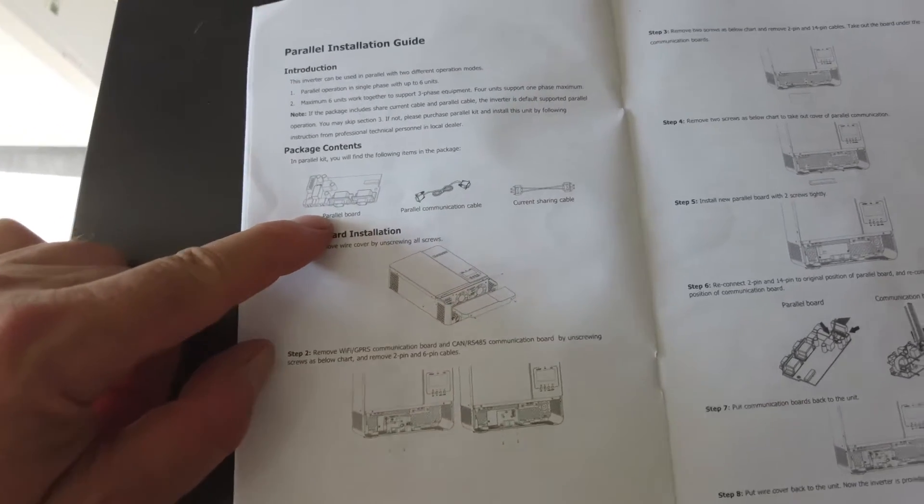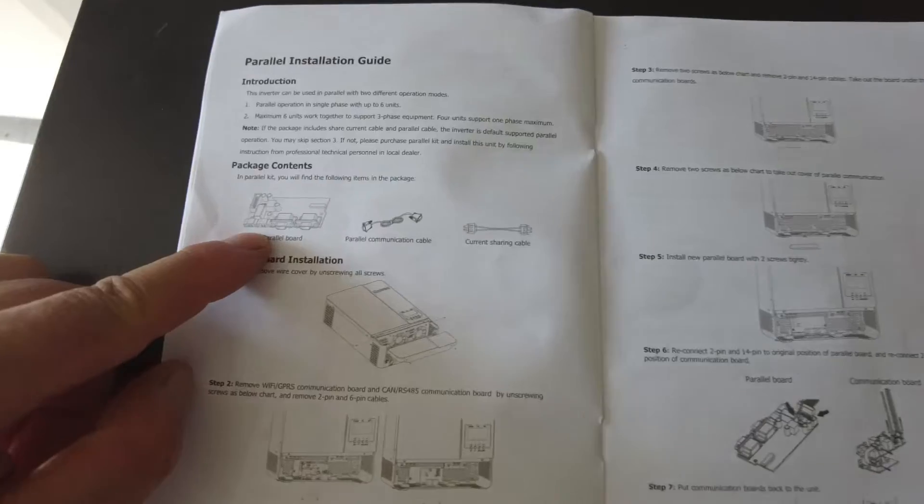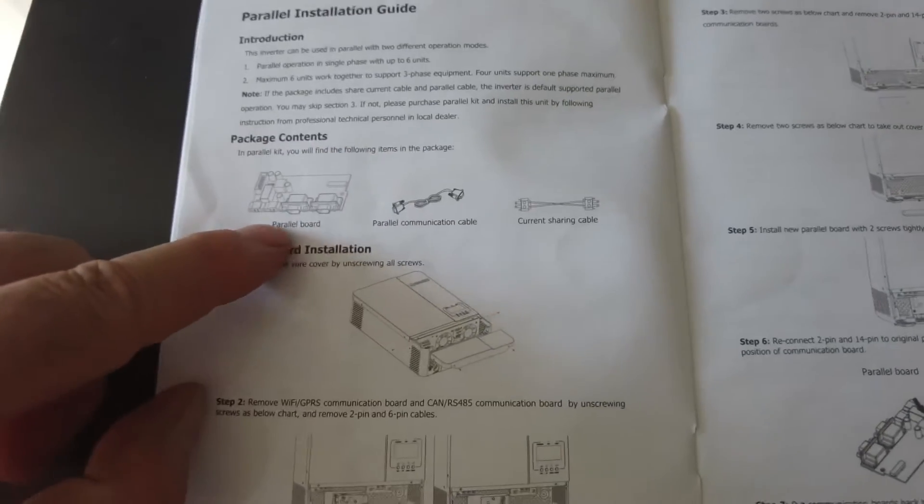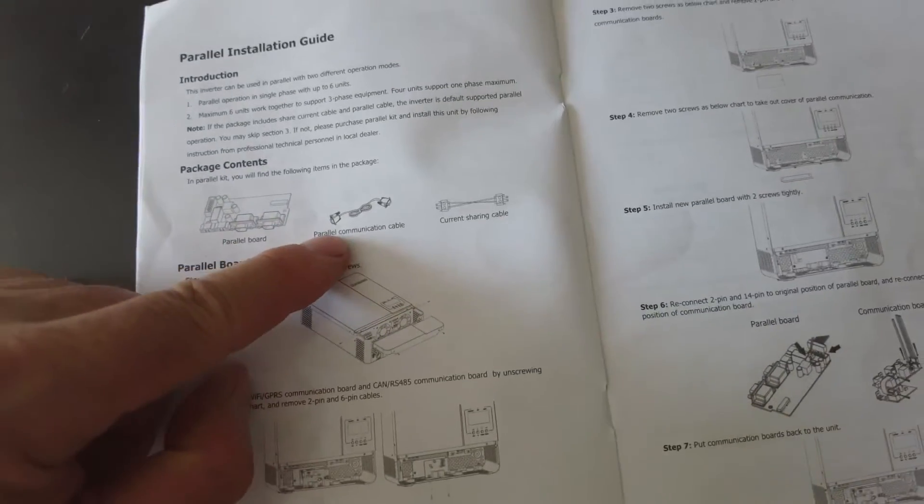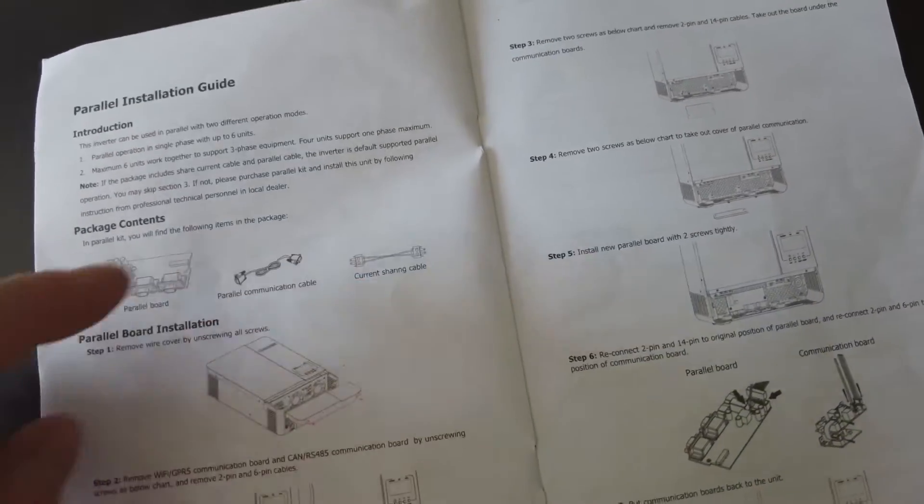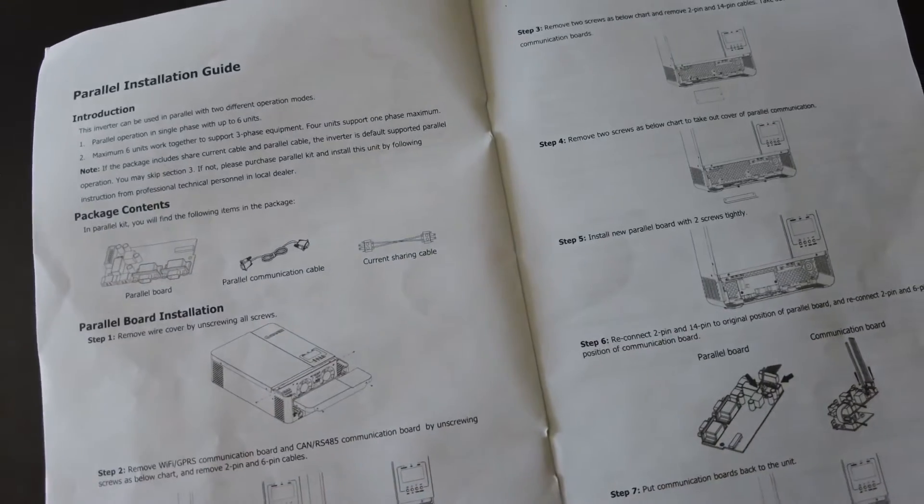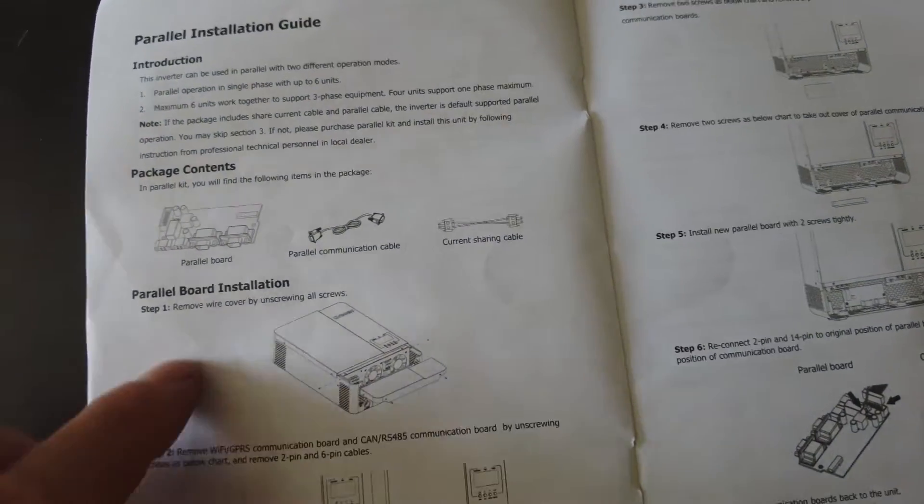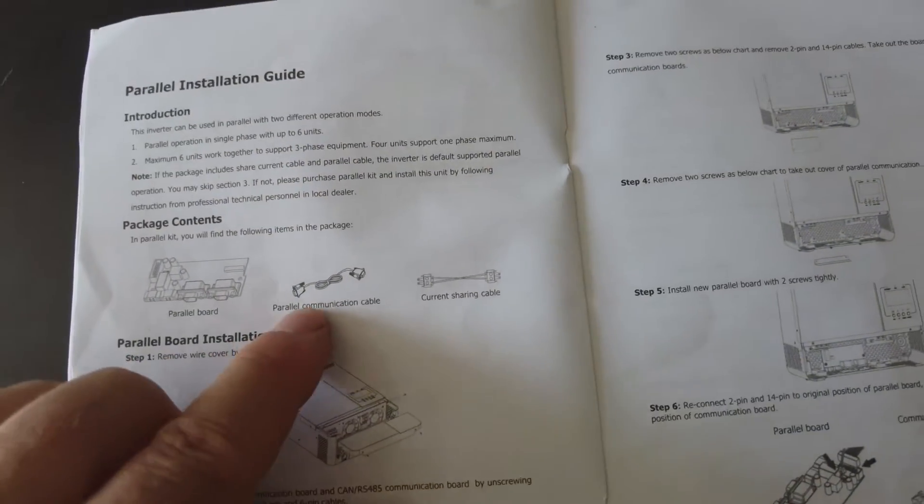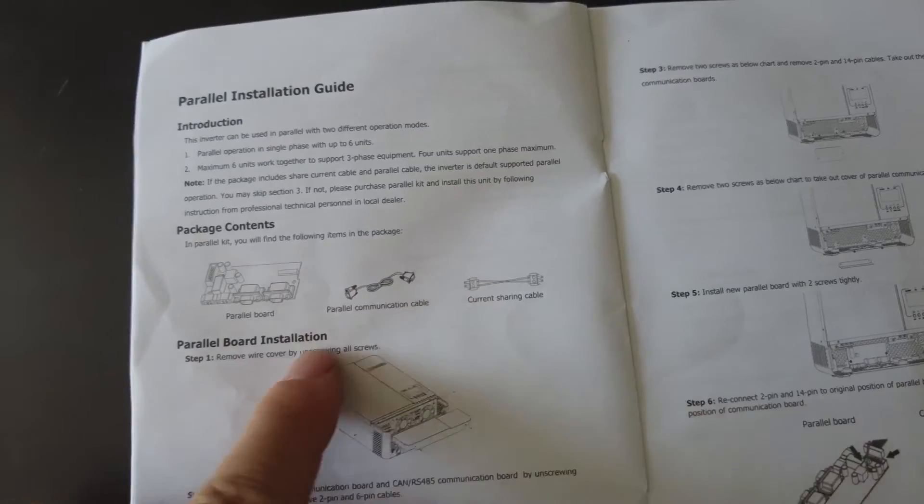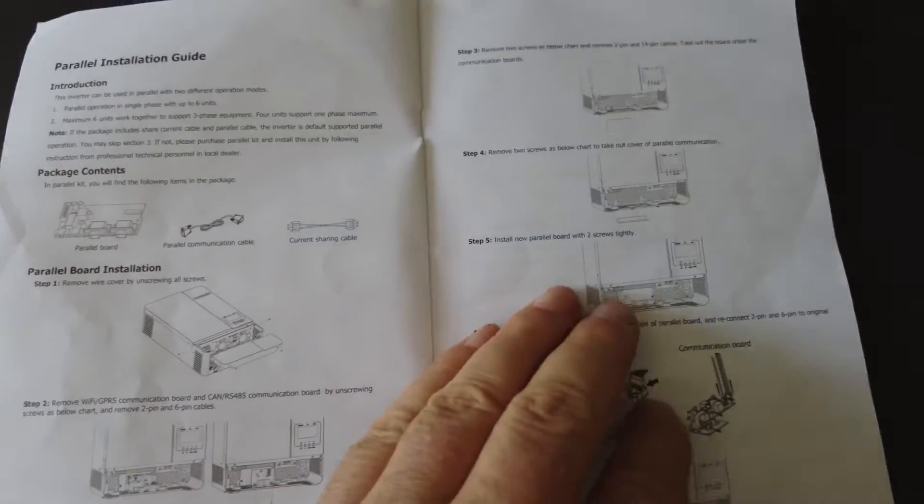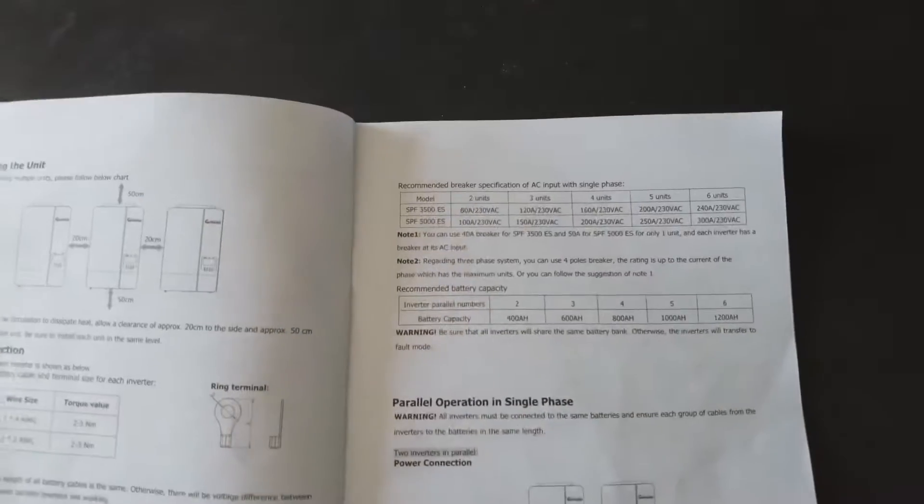And I believe that is correct because these connections are here. There is a parallel interface connection cable and a current sharing cable. So these are the cables that we are looking for. And I just want to check that my installer has installed them correctly. And I think that he has.